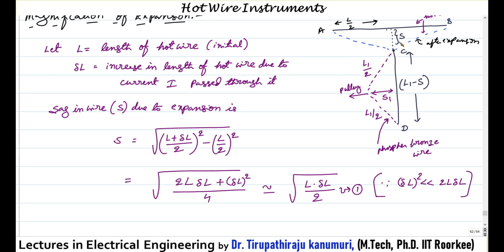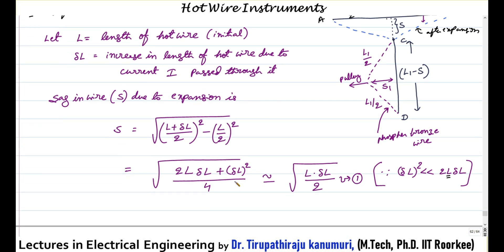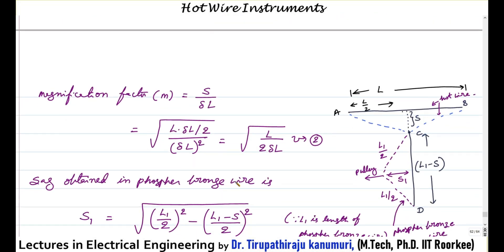From the right angle triangle we can calculate the sag. When simplified, it becomes 2L delta L plus delta L squared divided by 4, which is approximately equal to L times delta L divided by 2, since delta L squared is far less than 2 times L times delta L. Now, whatever small sag is coming, we want to further magnify it.